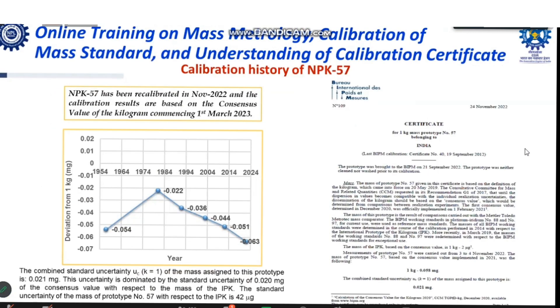NPK 57 has been recalibrated in November 2022, and the calibration results are now based on the consensus value of the kilogram commencing from the 1st of March 2023, which is the second consensus value. Looking at the trend, when we first received NPK 57, its nominal value was 1 kg minus 0.054 mg. With subsequent calibrations we found that value has been changing.